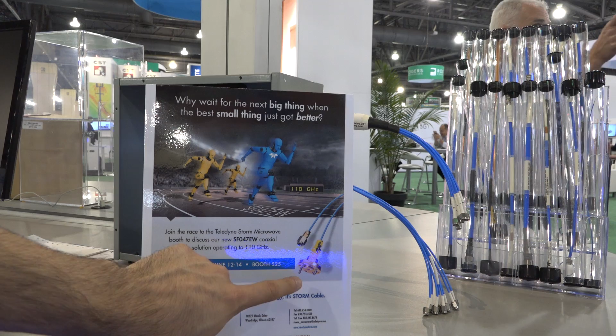One thing they have, which unfortunately I don't have an actual unit to show you, is this product where they have a flange, let's say a WR10 flange, going directly to a 1mm cable. So you have waveguide to coax conversion built directly into the cable itself. This gives you huge flexibility if you want to connect something that is waveguide to a 1mm cable, and still have the flexibility of moving the cable around. It's too bad they don't have one here for me to show you, but I'll definitely link to it on their website so you can look at the broad range of cables Teledyne makes. These are used not only in their products but in a lot of test and measurement. I think it's a nice catalog.